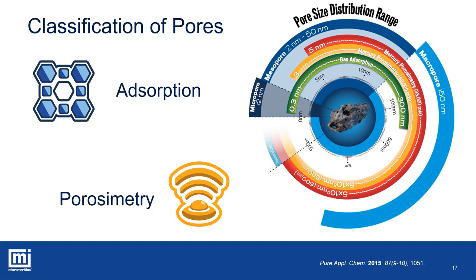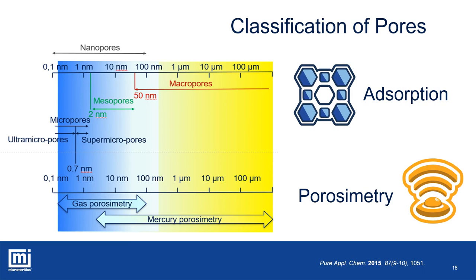Within the main pore size classification, additional subgroups have recently been identified, like the ultra- and super-micropores and nanopores. The gas physisorption technique allows the user to obtain specific surface area on virtually all materials independent of their pore size. Physisorption is used principally to determine pore sizes in the micro and mesopore size range, but it can also be useful for smaller macropores. Starting from about 3 nm, mercury porosimetry completes the information on pore sizes up to more than 650 microns, depending on the nature of the sample and the pore. Both techniques are commonly used for characterization of catalysts and catalyst supports.